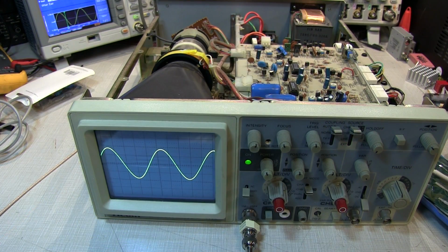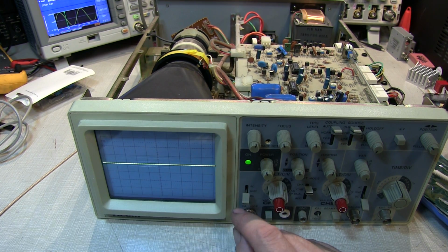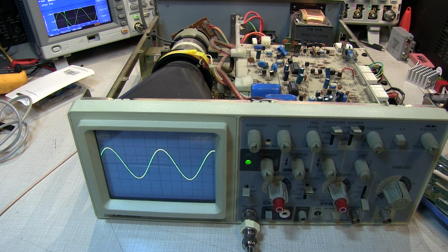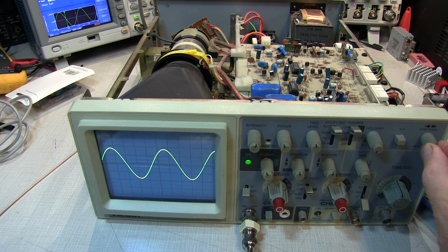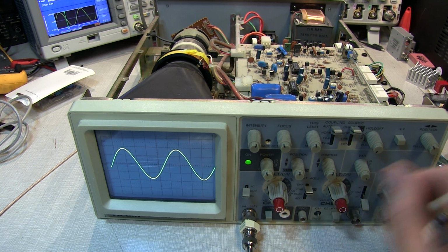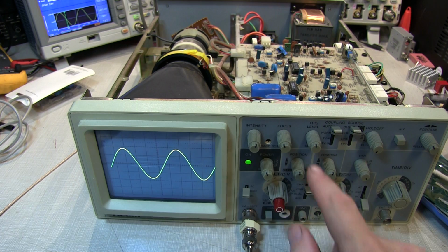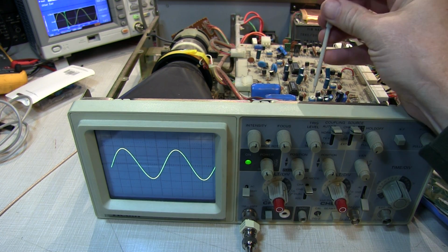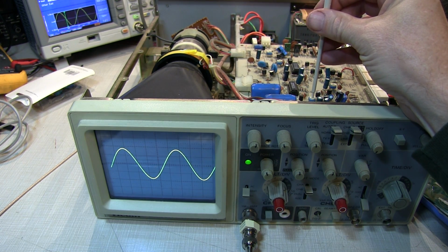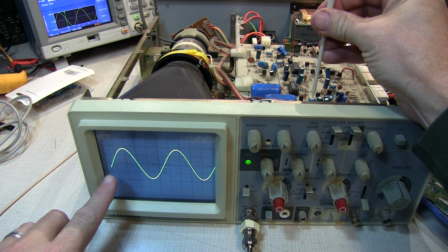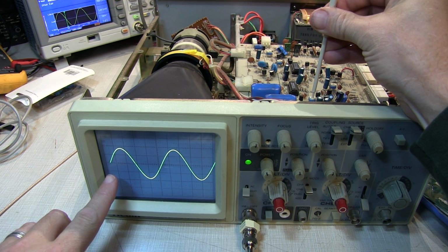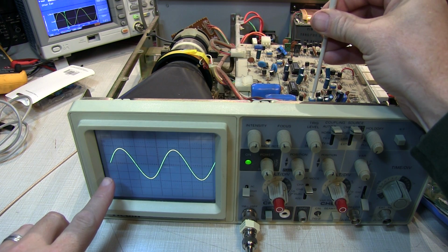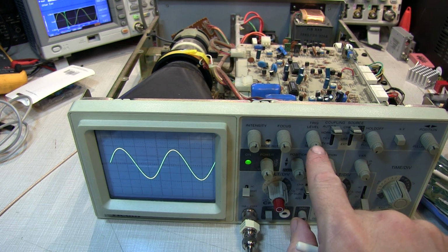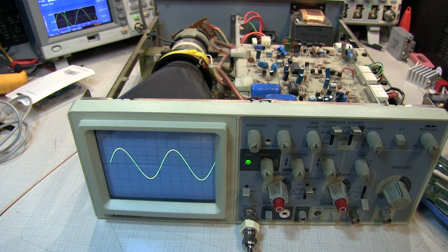Okay, the next adjustment is to the trigger offset. We apply a 1 kilohertz sine wave to the input, AC coupled, to make sure that the signal is centered on the screen. We'll adjust the horizontal position so that we can see where the waveform is being triggered. Set the trigger control to its mid position and adjust the trigger offset control until the waveform basically starts right at mid scale. Right there. So that will ensure that the midpoint on the trigger level is the midpoint on the screen.